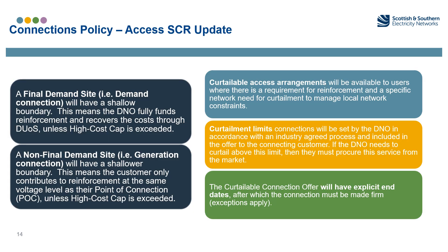Let's look at these elements in more detail. First, let's look at the shallower boundary. For a final demand site, i.e. a demand connection, there will be a shallow boundary. This means the DNO fully funds reinforcements and recovers the costs through DUOS unless a high cost cap is exceeded. For a non-final demand site, i.e. a generation connection, there will be a shallower boundary. This means the customer only contributes to reinforcement at the same voltage level as their point of connection, again unless a high cost cap is exceeded.